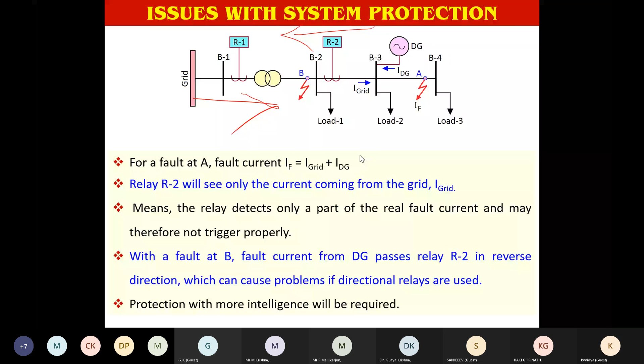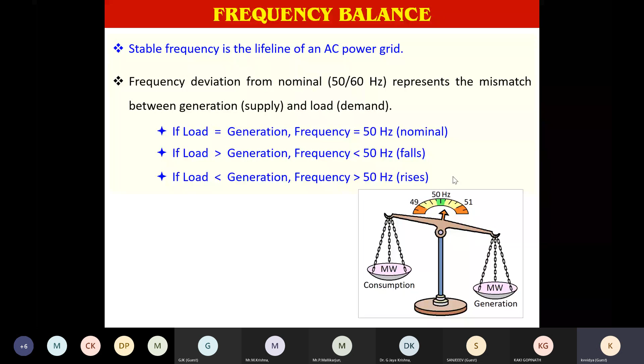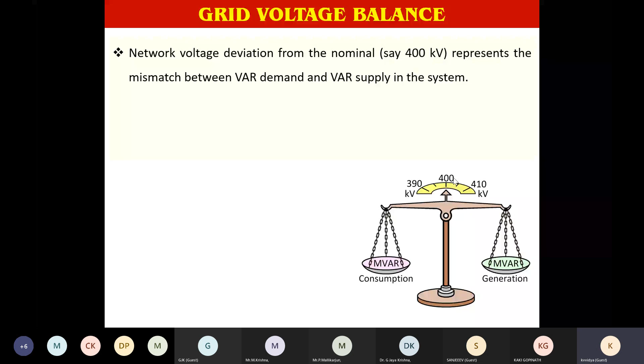Then another most significant aspect is grid support by generators by way of frequency and voltage, because once your generator is grid connected, we have two important roles: supporting the frequency regulation and the voltage regulation. And for that, we have various controllers. We know that system frequency balance is maintained because of the energy balance, because the active power balance represents the frequency deviation. If the megawatt supply is more than the demand, frequency goes up. And if the megawatt demand is more than the supply, frequency comes down. And there is a device called a governor in any prime mover, and the function of the governor is to balance this mismatch between the supply and demand, megawatt, real power, active power. Likewise, we have the excitation. The purpose of the excitation, after the grid synchronization of the machine, is actually voltage balancing. Because sometimes voltage falls, so we increase the supply. If the voltage is high, we reduce it.